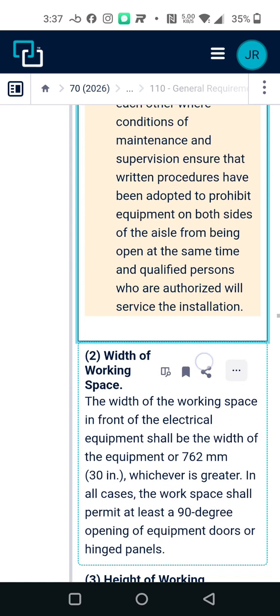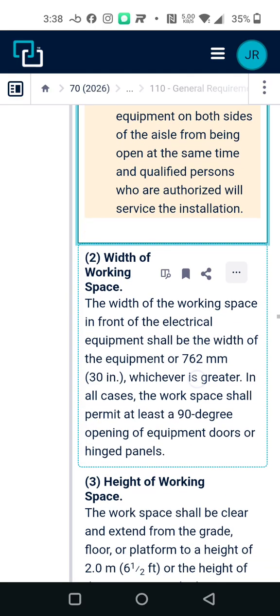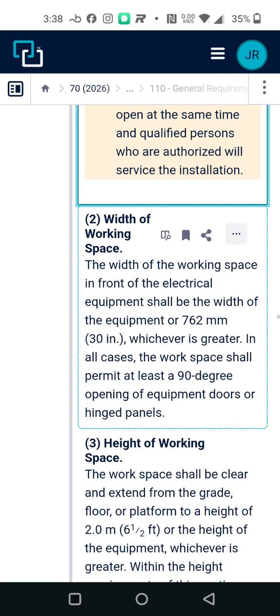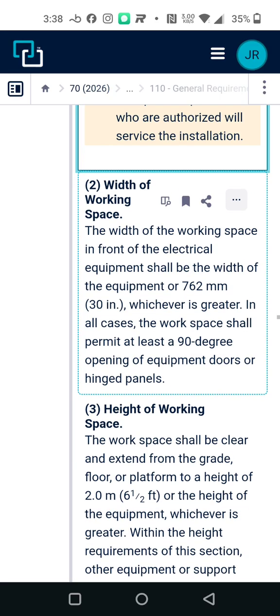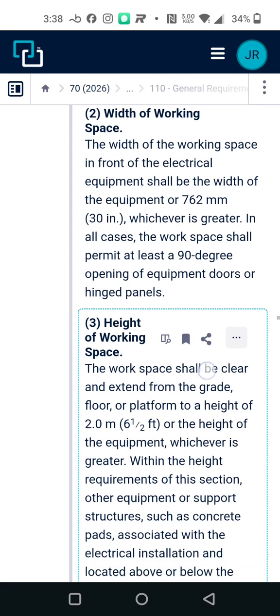Okay. Width of working space. The width of the working space in front of the electrical equipment should be the width of the equipment, or 762 millimeters, whichever is greater. In all cases, the working space should permit at least a 90-degree opening of equipment doors or hinged panels.